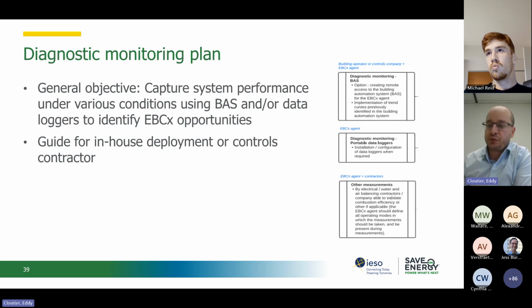Obviously, by observing the systems operating with the building control system, it's possible to see this information from time to time. But when we collect the data over a long period of time, we will see trends or problems appear that are difficult to see instantly at a glance when you're in front of the operating station.